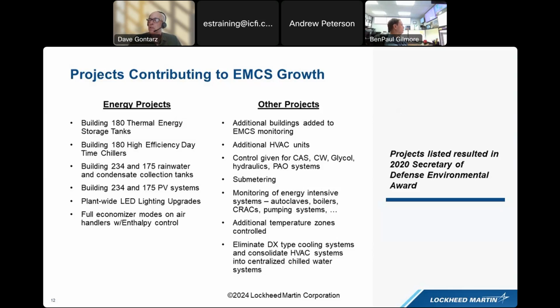I'd love to hear a little more about that recognition, Ben Paul. That was a multi-project that was put together. Our primary contributions were a large 2 million gallon thermal energy storage tank, rainwater harvesting where we collect almost 10 million gallons of rainwater and condensate water off our air handlers every year to reduce water consumption, PV systems, a massive LED lighting upgrade in our factory and warehouse production areas, and optimizing economizers across the site.